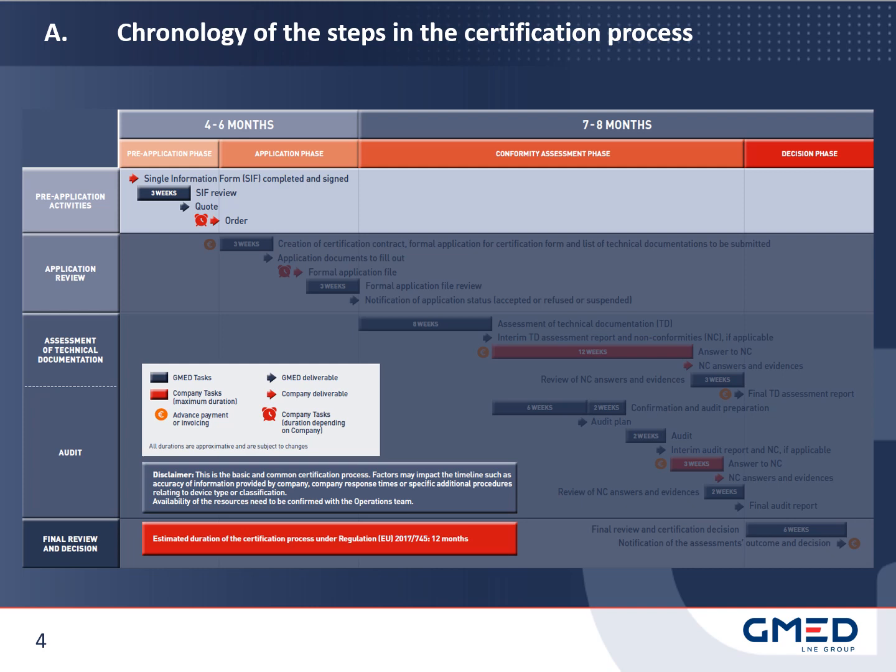After receiving this form, GMED teams analyse the SIF in order to provide the manufacturer with the quotes for the conformity assessment services to be performed. The duration relative to the analysis of the SIF, completed in a satisfactory way by the manufacturer, and the realisation of activities necessary to conclude the corresponding estimates is estimated at 3 weeks. Upon receipt of the quotations, the manufacturer places an order with GMED, thus completing the pre-application phase.